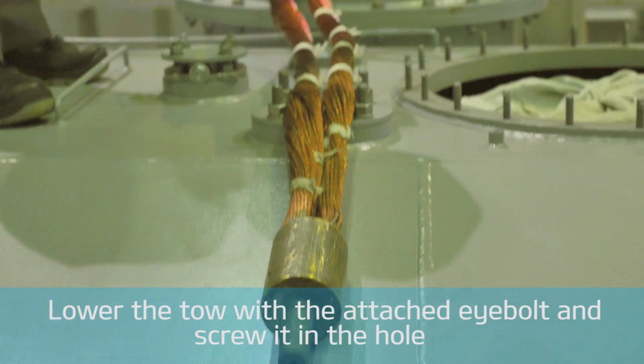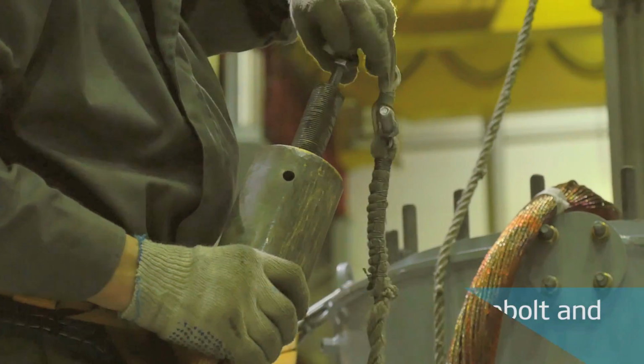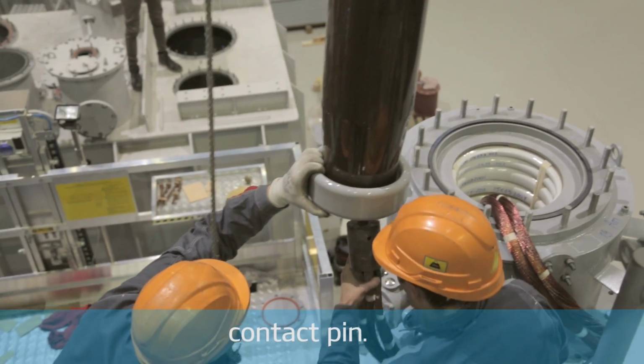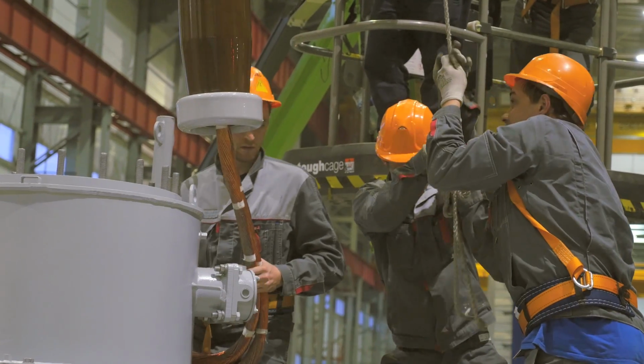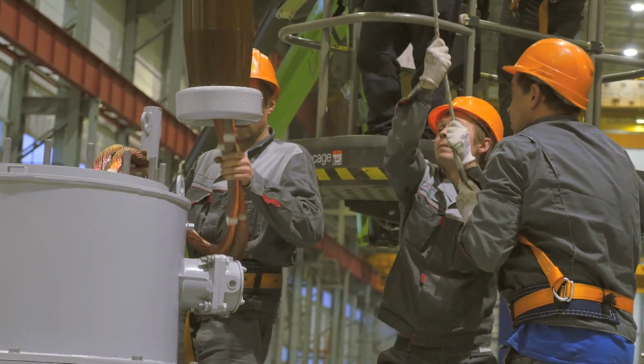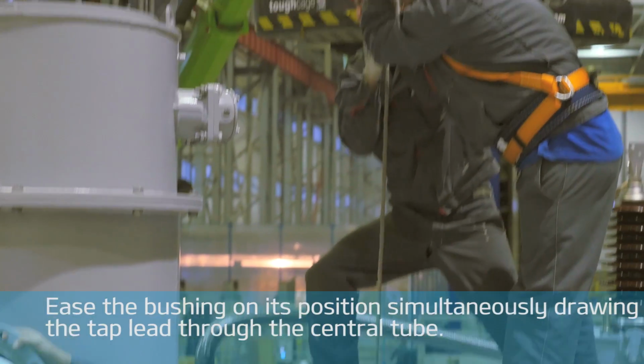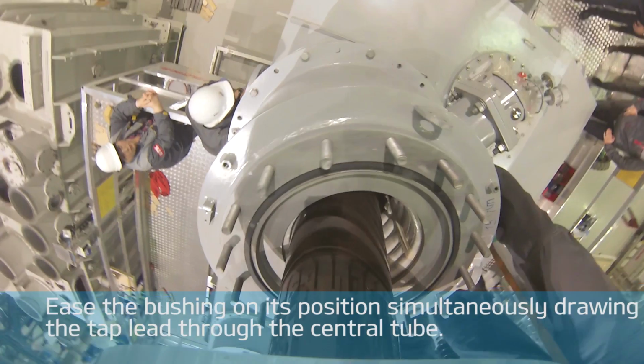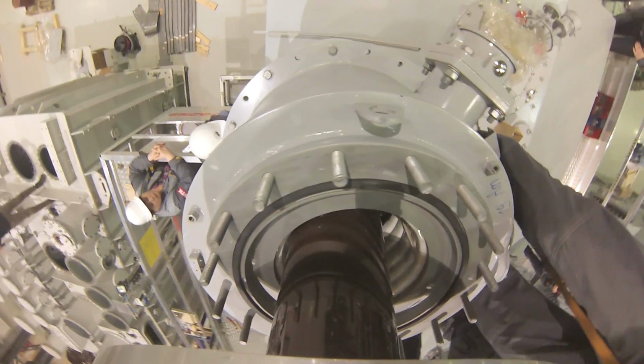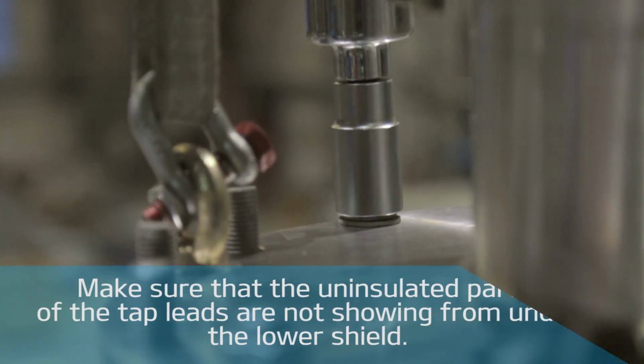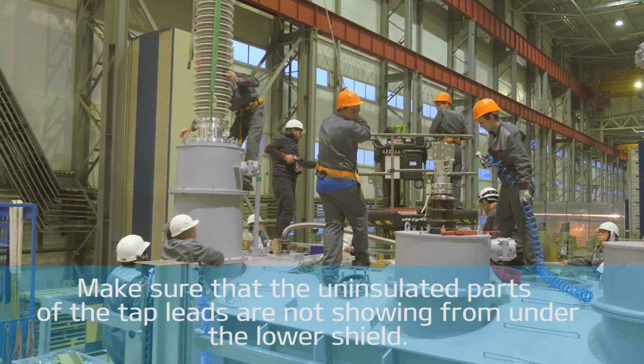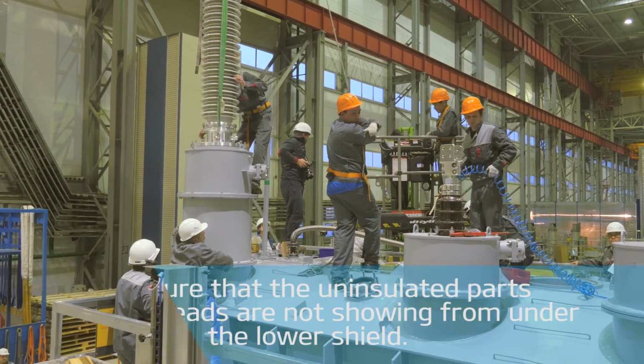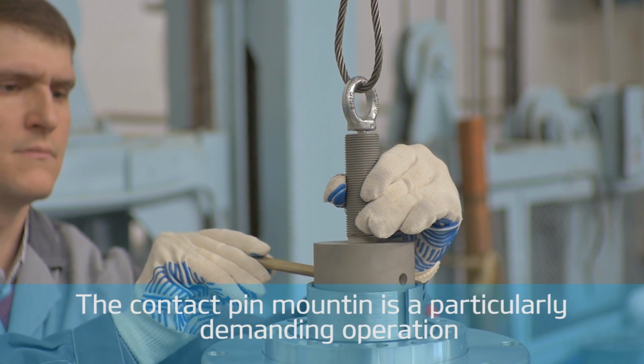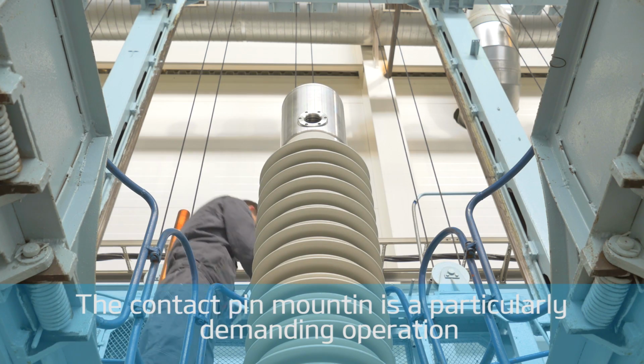Lower the tow with the attached eye bolt and screw it in the hole of the preliminary solder to the transformer tap lead contact pin. Put the contact pin inside the central tube of the bushing and hold the loose end of the tap lead in. Now carefully ease the bushing on its position, simultaneously drawing the tap lead through the central tube. Control the lead entrance to the tube through the transformer access cover. Make sure that the uninsulated parts of the tap leads are not showing from under the lower shield. And then do the final tightening of the bushing in the transformer.